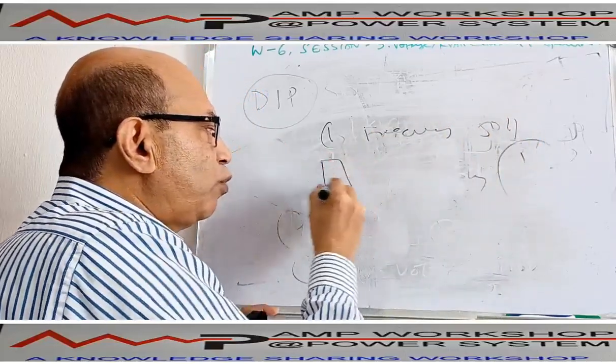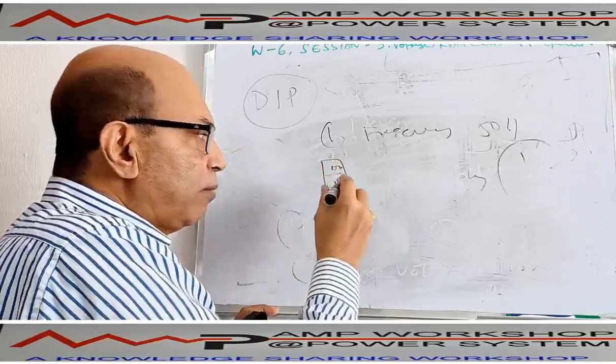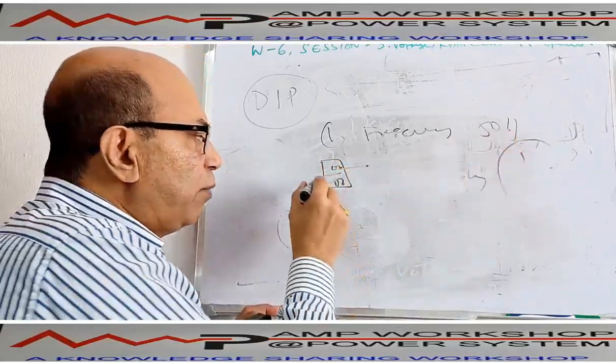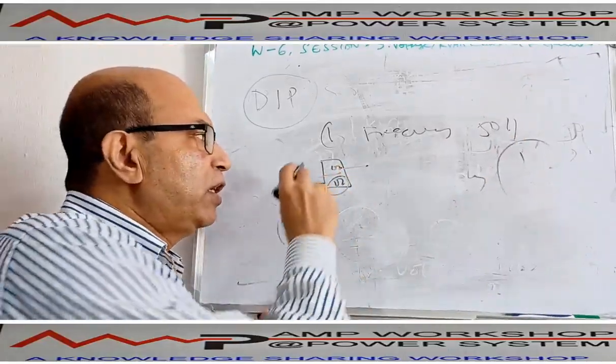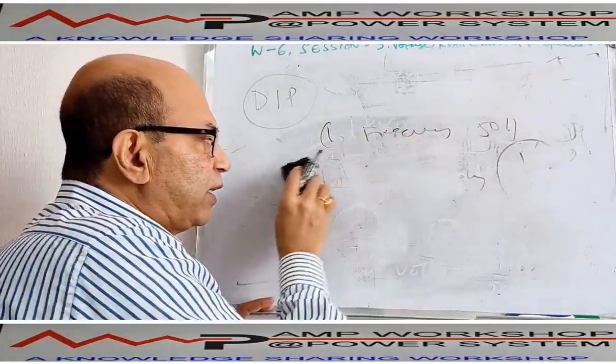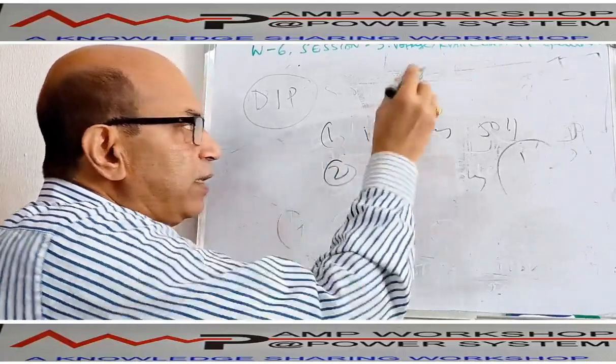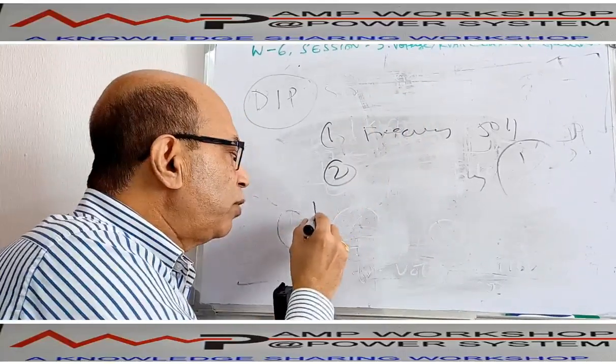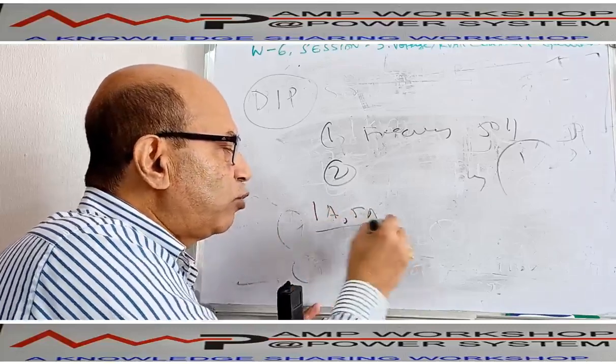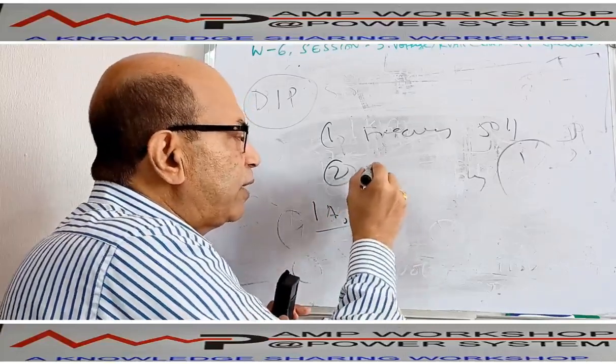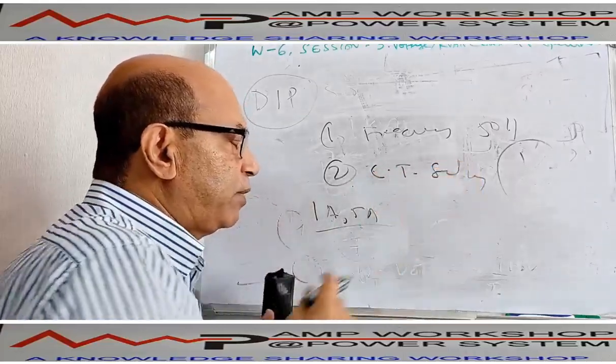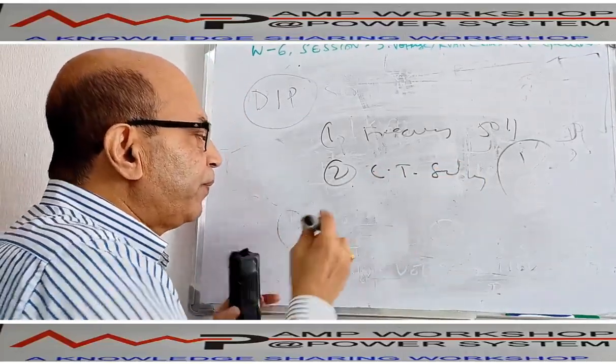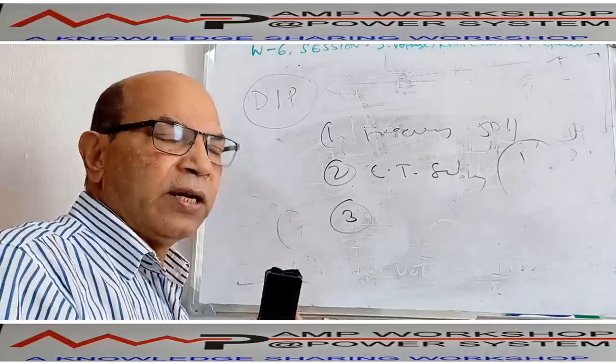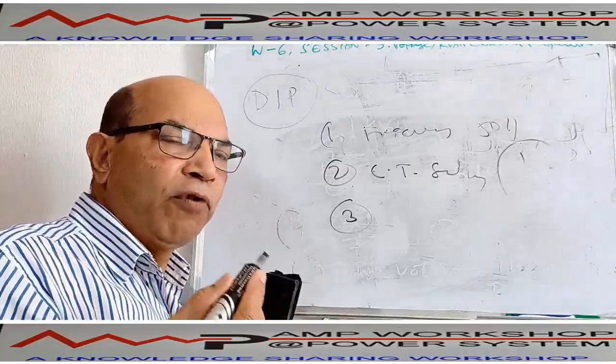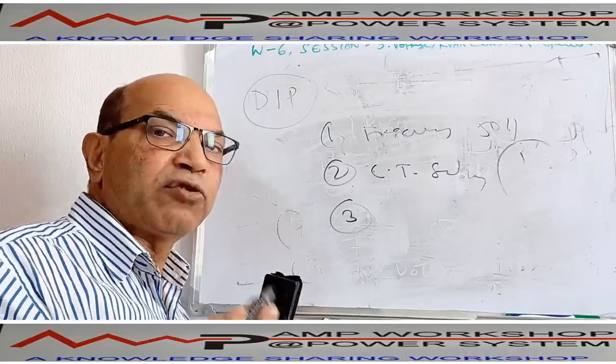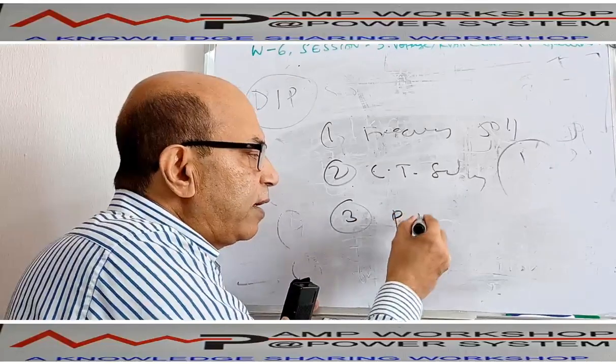A DIP switch has two positions, on position or off position. So suppose if you put it in on position, it may be 60 hertz. If you put it in off position, it will work as 50 hertz. So this way, there is one DIP switch for the frequency selection. Then the second DIP switch, we have already said there is a cross current CT. The CT could be 1 ampere, it could be 5 ampere. So there are two values possible. So there is another DIP switch for the CT selection. Then the third DIP switch, you know, this PT supply which you are taking can be of different values. It could be 400 volt, it could be 120, it could be three phase, it could be single phase. So for that selection also, there is another DIP switch.